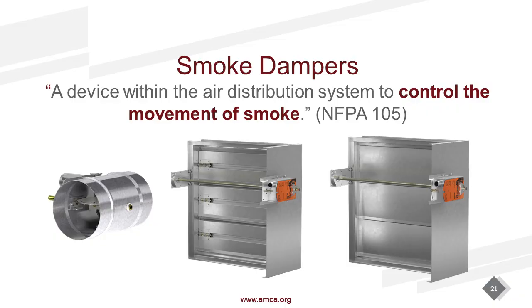There it is. Pretty simple. We are controlling the movement of smoke. Now we use the word movement, so we know the air is always moving. Smoke dampers are always considered dynamic. They have an actuator. They will have a velocity and a pressure rating.